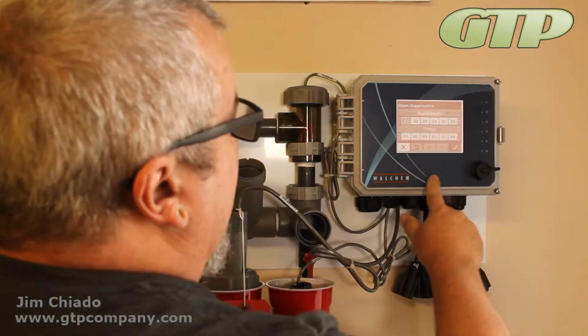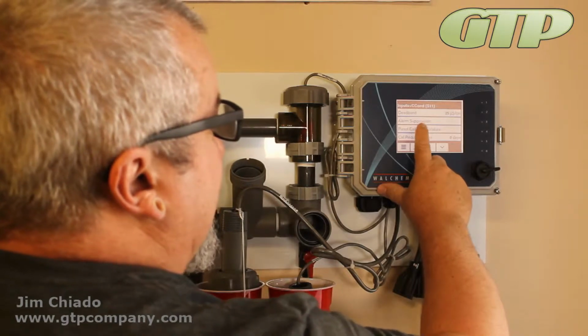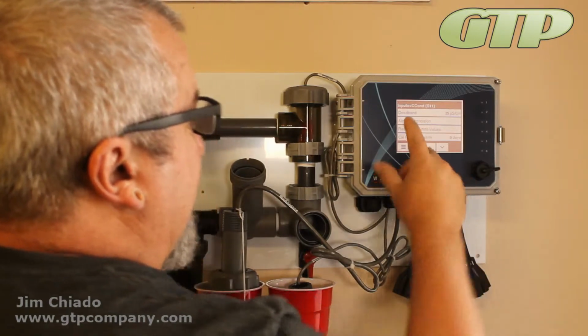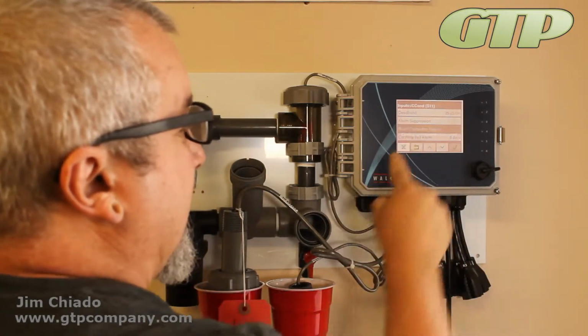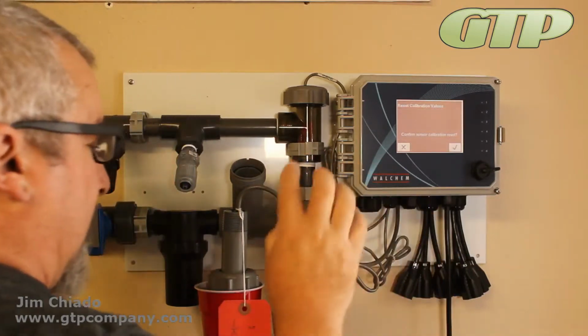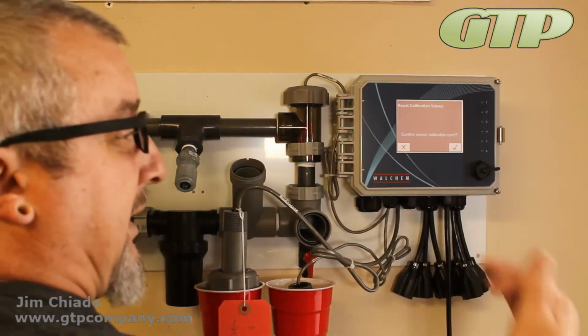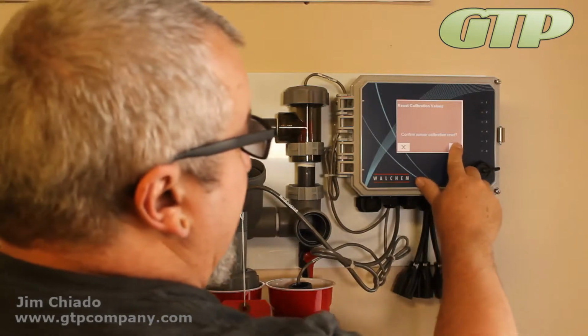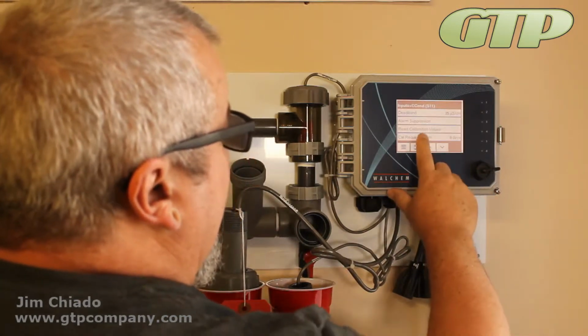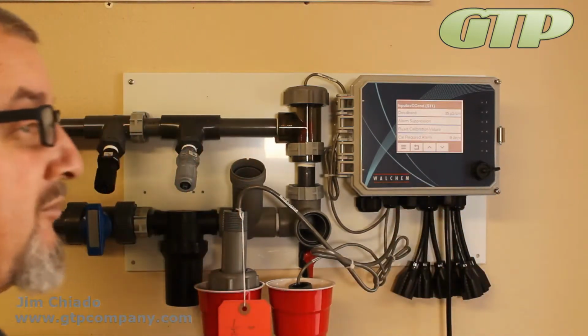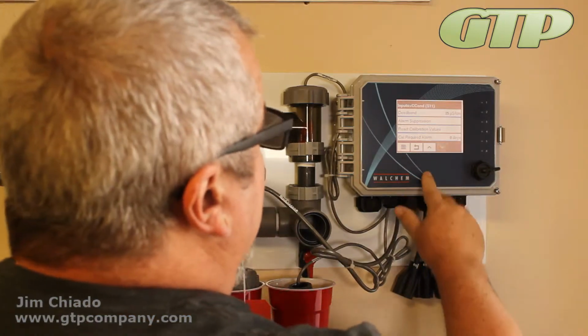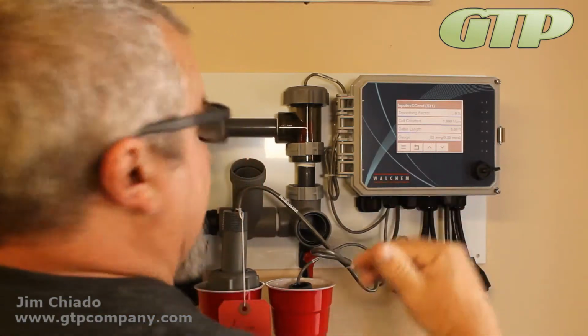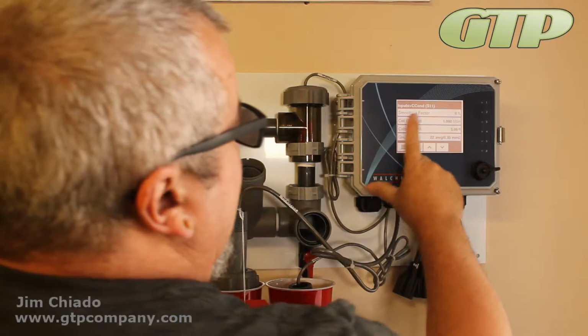Other than that, the only one that I would have set on the alarm suppression is reset calibration values when you're switching sensor. This one here is very important to do. You're rechanging the sensor, you don't want to go back on the old habits, you want to start all fresh and new. Just hit the check mark. Cal required: it will remind you in 20 days, 30 days that you need to do a calibration. You guys really should be doing it on your regular maintenance.